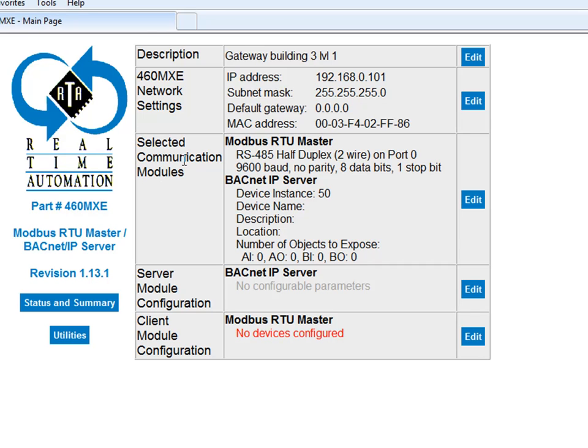Next, we'll get to our selected communication modules. In this device, we're going to have a Modbus RTU master. That's the protocol, the master protocol that's going to connect out to those power meters. And we're going to have a BACnet IP server. That's how we're going to produce this data so that it can be scanned by a BACnet IP client.